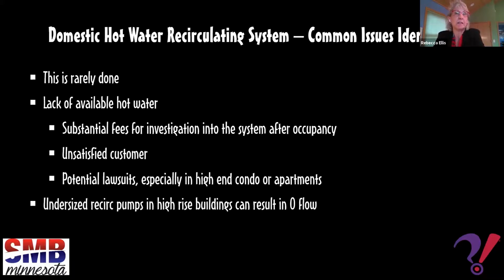So lots of stuff rides under the radar for construction projects and contractors that, if you're not taking care of them at the end of the project, may very well come back to you in a few years if they start having problems with domestic hot water delivery. One of the reasons that the plumbing system is not done is a lot of times it's not even specified by the design engineer to do that, other than the circulating pump.